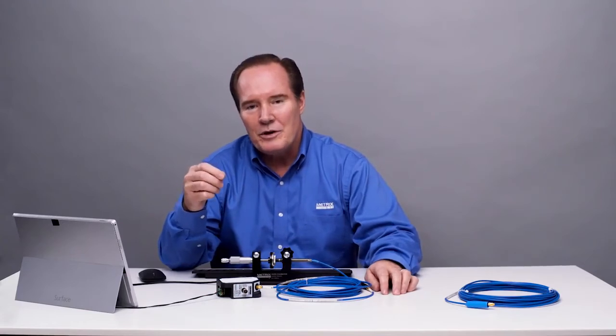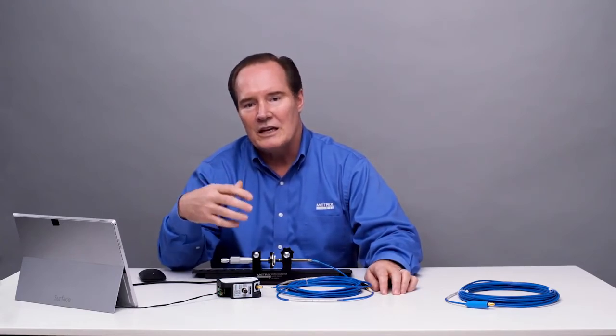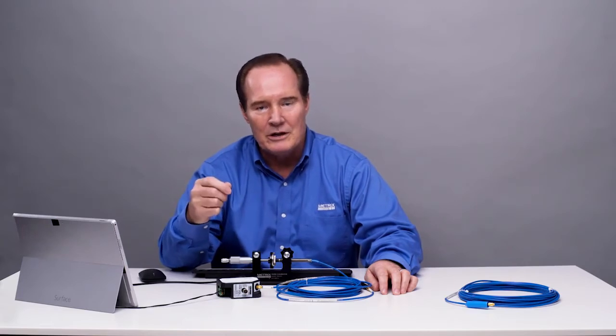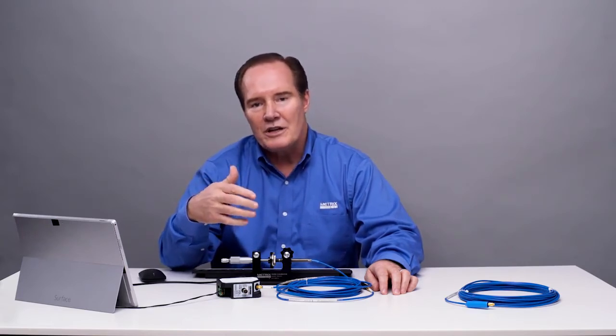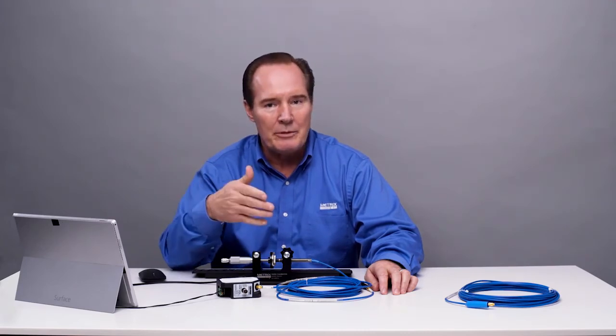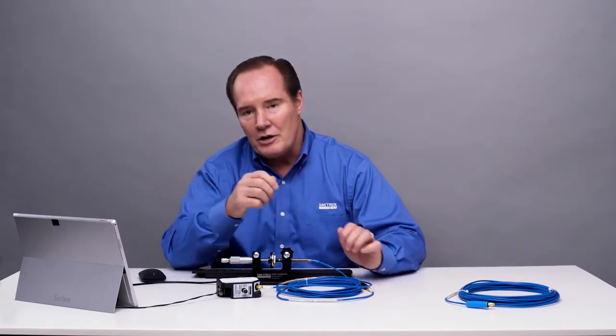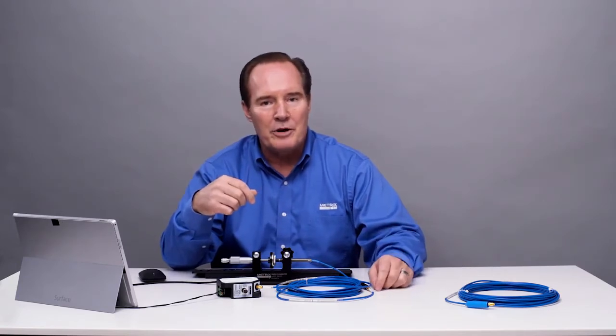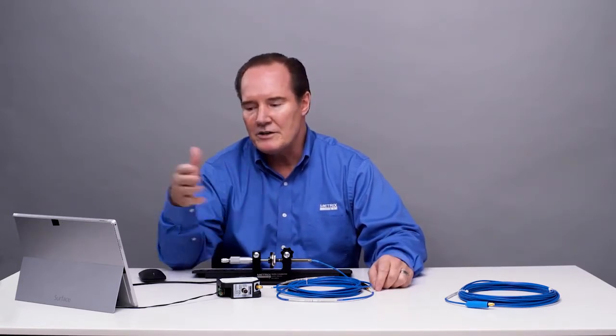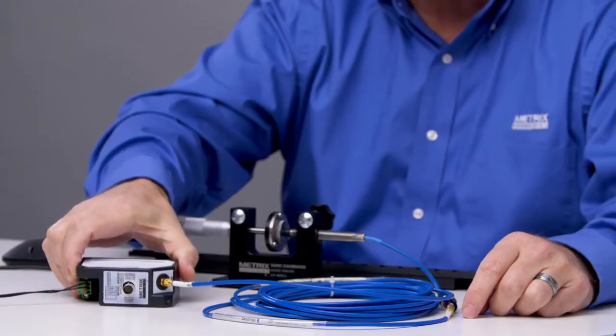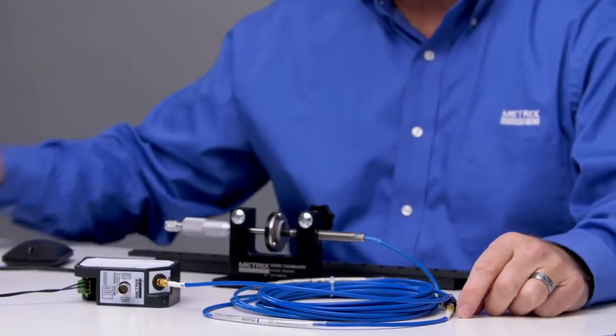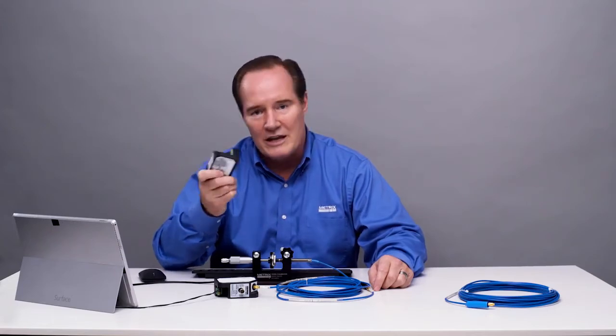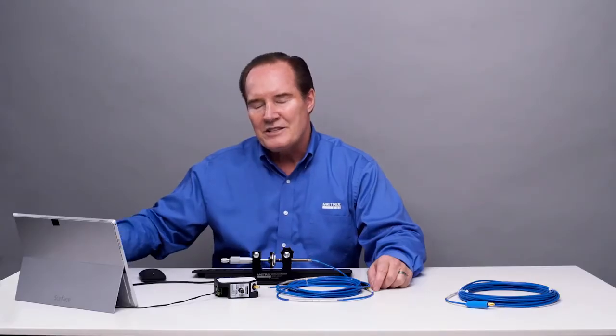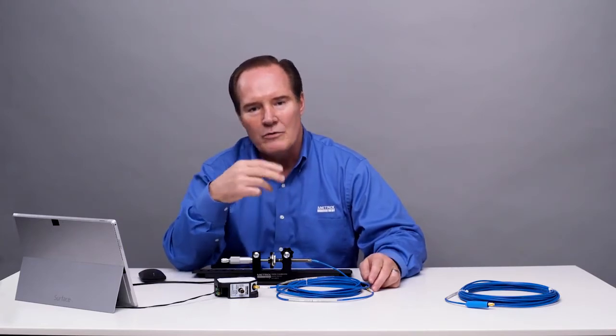But in our case, we can reprogram it to the system length you want. And in a previous video, we discussed how to trim a cable. The purpose of that was if you took a 9-meter cable and made it into a 7-meter cable by cutting off 2 meters, you could then put on a new connector and run a calibration and see if it worked. What I have here is a Metrix digital proximity system. This happens to be one of our transmitters, but you can do the same thing with one of our drivers. It can be with a driver or transmitter. The same process holds. I have a 9-meter cable, and I cut off 2 meters so I can get rid of that coil of wire inside the cabinet.